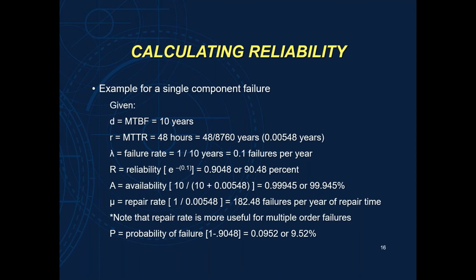When we take these values and factor in the time that we're out of service, we have what's known as the availability. And if you look, the availability number on this one component is actually very high. The reason it's high is because even though it may fail every 10 years, the outage time is only 48 hours. So on average, you're 99.945% available on that system for that component.